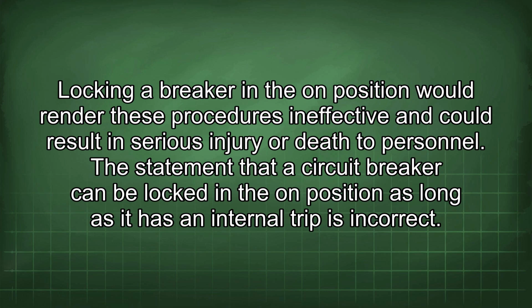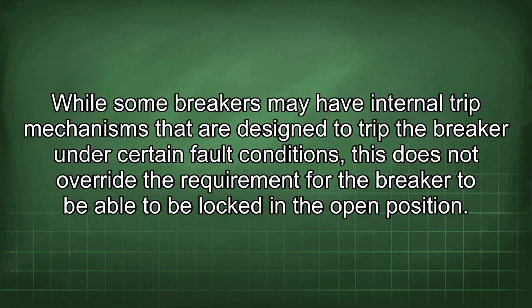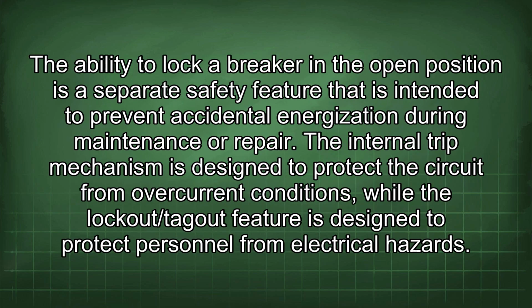The statement that a circuit breaker can be locked in the on position as long as it has an internal trip is incorrect. While some breakers may have internal trip mechanisms that are designed to trip the breaker under certain fault conditions, this does not override the requirement for the breaker to be able to be locked in the open position. The ability to lock a breaker in the open position is a separate safety feature that is intended to prevent accidental energization during maintenance or repair.